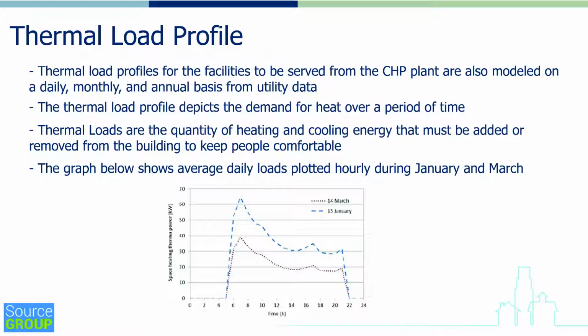Some people would use steam charts to do that. However, it's probably not recommended because steam's very difficult to actually measure when there are variations in flow. So generally, for thermal load profiles, gas meter data is used, and that indicates how much gas is being used over an hour at a particular point in the day, and those vary, again, with time of day and the day of the week.